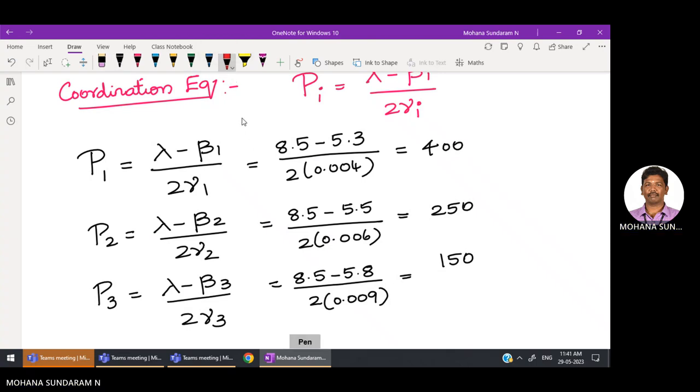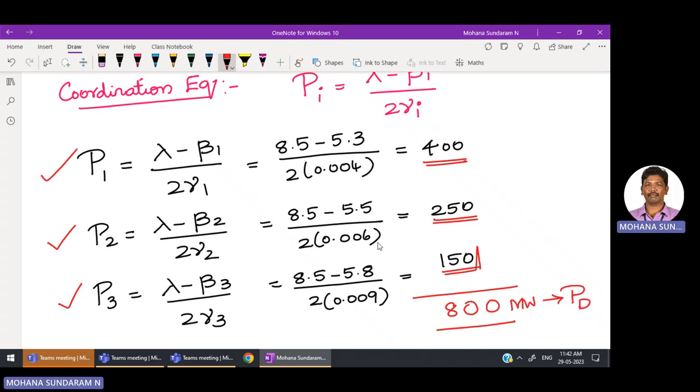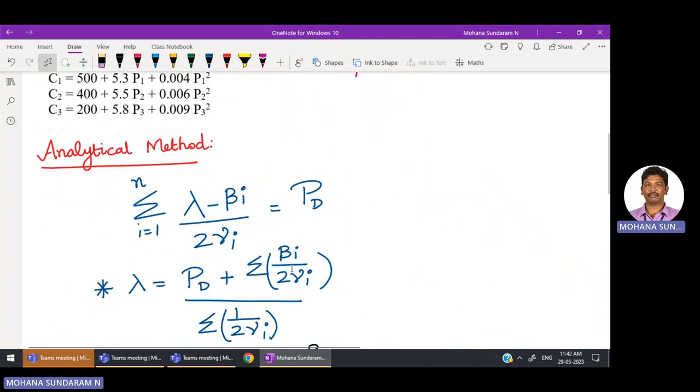So what do you understand from this? In order to get the lowest operating cost, you have to operate power plant 1 to generate 400 megawatts, power plant 2 to generate 250 megawatts, and power plant 3 to generate 150 megawatts. All together, it is 800 megawatts, so our load demand is met. This is the optimal way of operating the three power plants so that the entire total operating cost will be the least one.